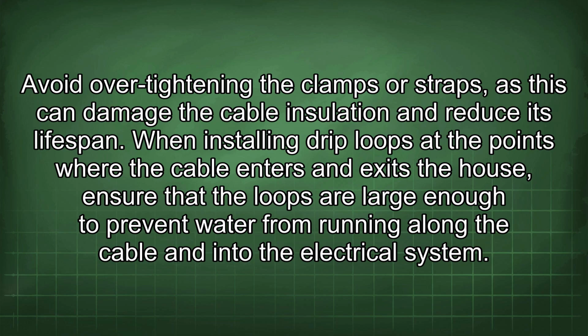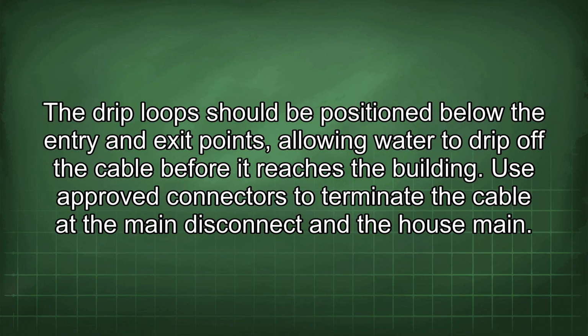When installing drip loops at the points where the cable enters and exits the house, ensure that the loops are large enough to prevent water from running along the cable and into the electrical system. The drip loop should be positioned below the entry and exit points, allowing water to drip off the cable before it reaches the building. Use approved connectors to terminate the cable at the main disconnect and the house main.